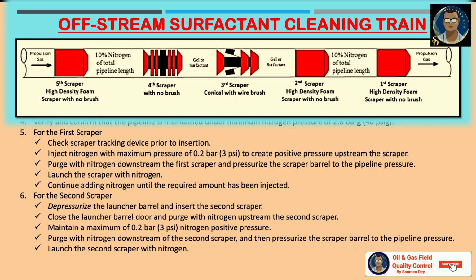Maintain a maximum pressure of 3 psi, nitrogen positive pressure. Purge with nitrogen downstream of the second scraper and then pressurize the scraper barrel to the pipeline pressure. Finally, launch the second scraper with nitrogen.